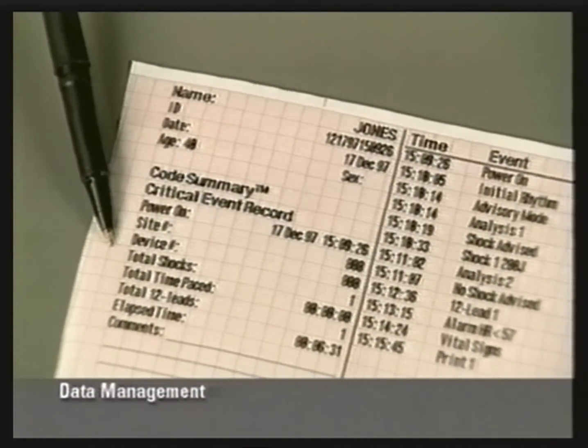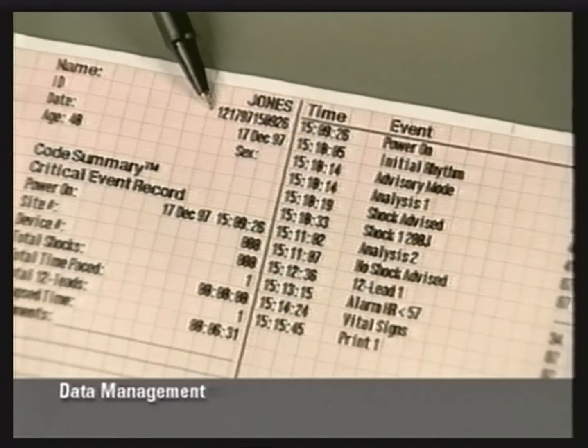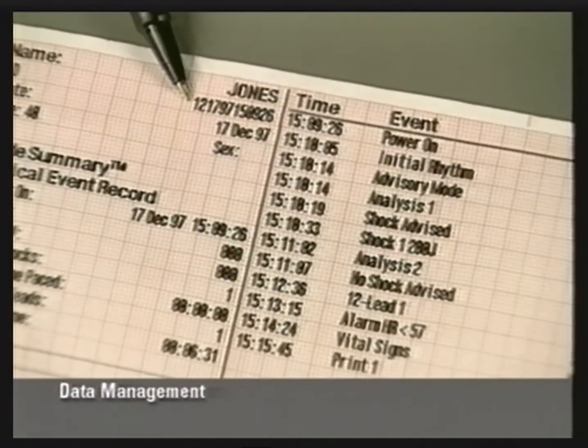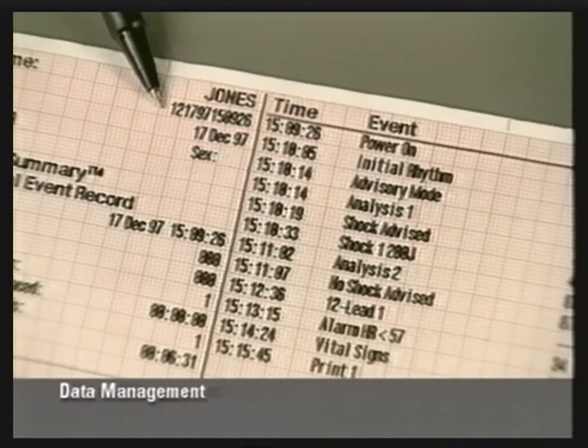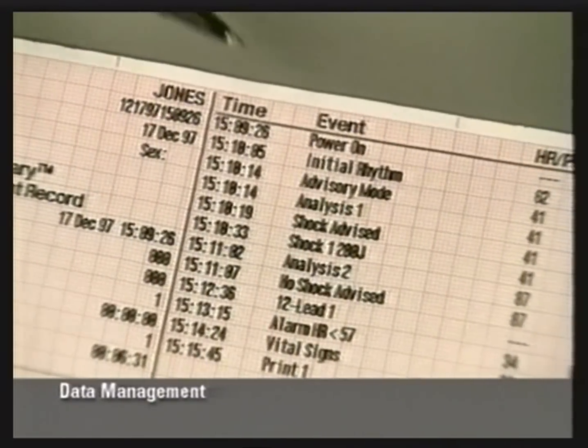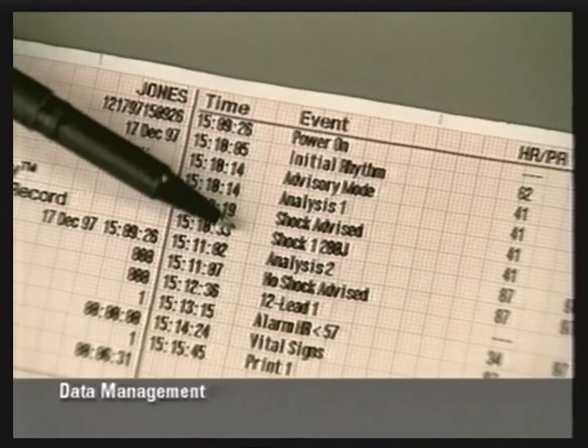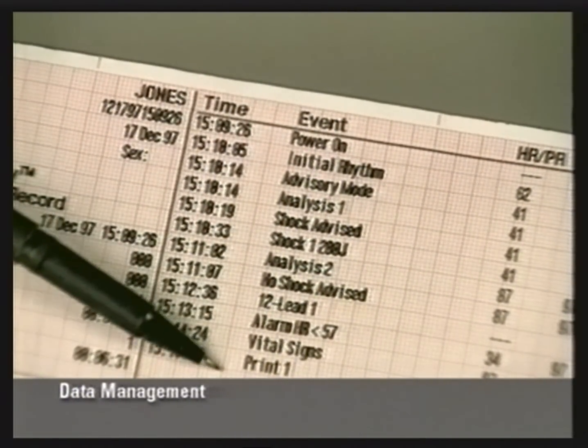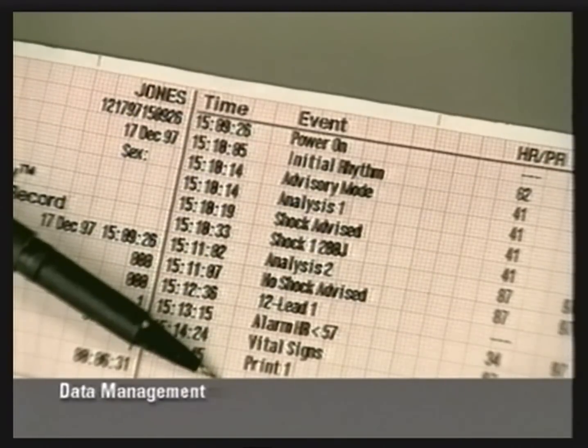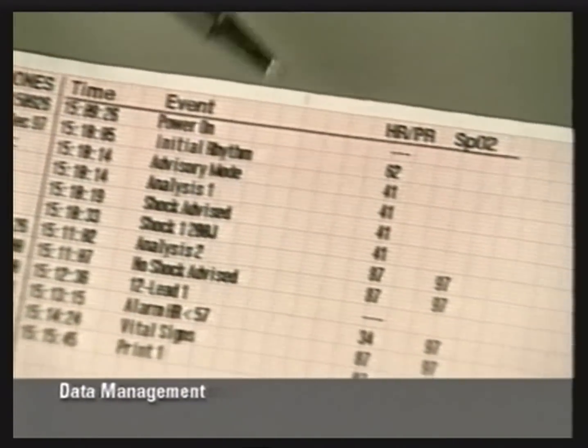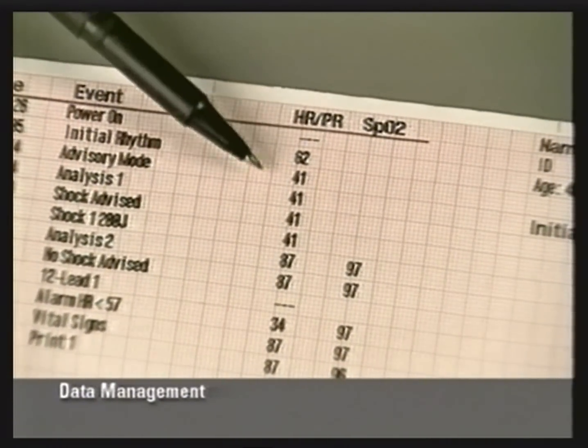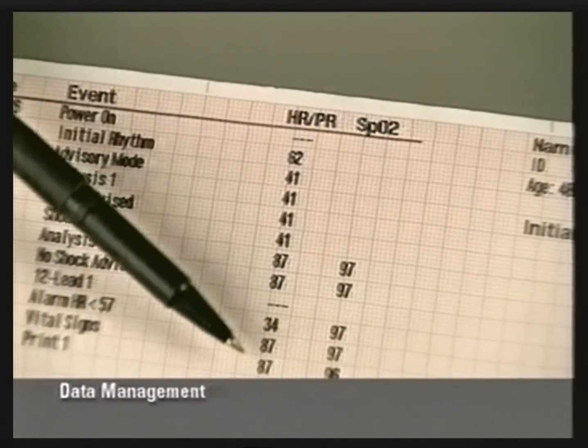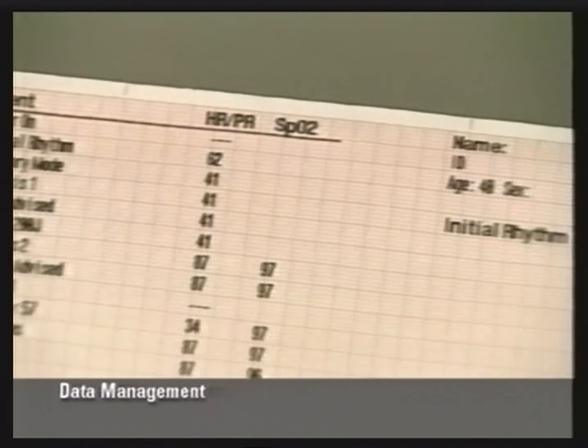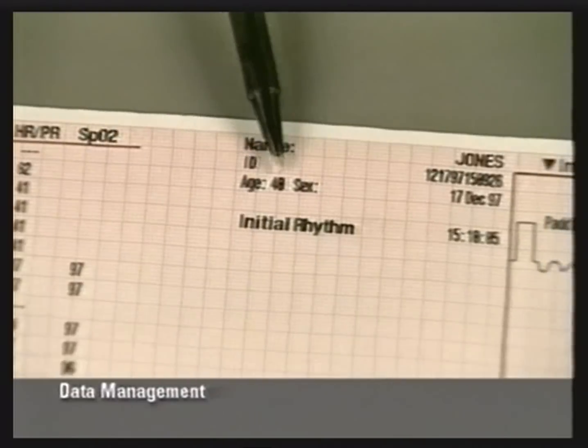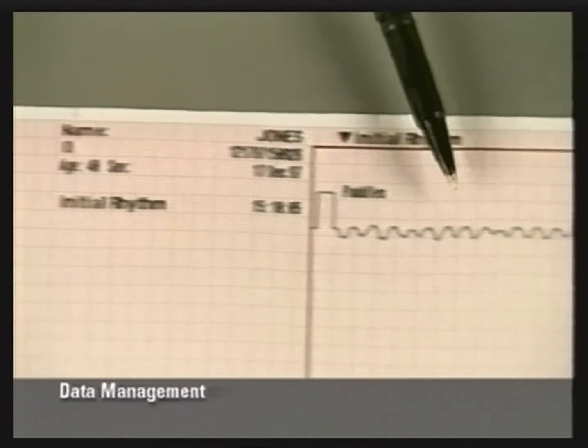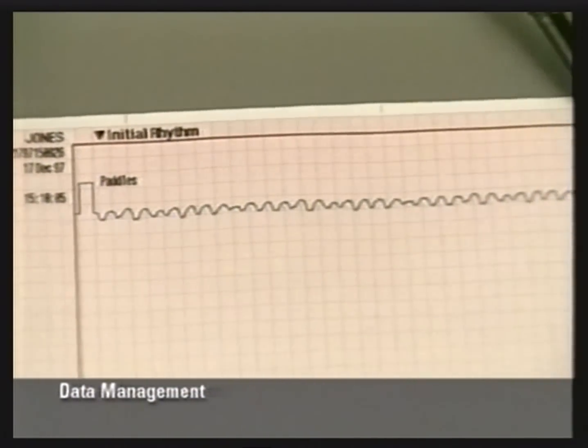The defibrillator automatically enters a unique ID number for each patient, composed of the date and time the defibrillator is turned on. The event vital sign log documents device and operator actions related to monitoring, therapy, data transmission, and more. Vital signs are also listed for each monitored parameter. Events and vital signs are listed in chronological order. Waveform events include header information and the ECG associated with that event.